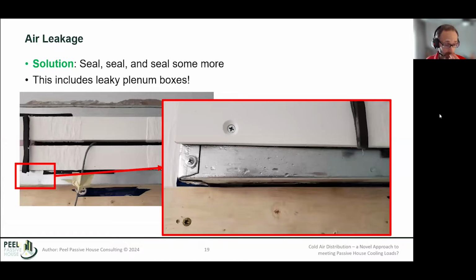But the air leakage wasn't just at the diffuser, there were leaky plenum boxes too, it just shows up wherever you have leaks. This is an insulated plenum box, they've insulated all the interior surfaces, so this isn't really conduction, this is really air leakage.